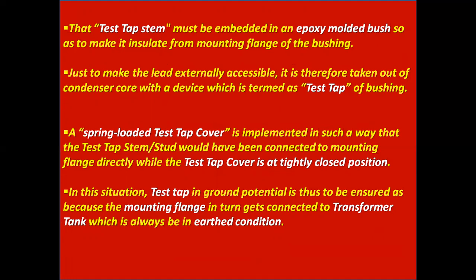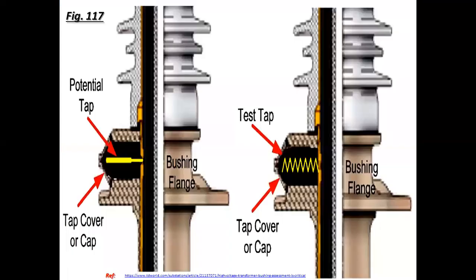A spring-loaded test tap cover is implemented in such a way that the test tap stem or stud is connected to the mounting flange directly while the test tap cover is in the tightly closed position. In this situation, the test tap is ensured to be at ground potential, because the mounting flange in turn is connected to the transformer tank, which is always at earth condition. See the diagram of potential tap and test tap.